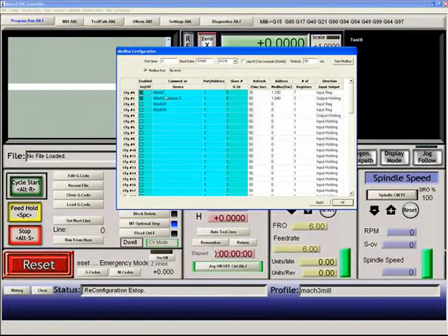These names are usually read by a plugin, and they're really just there as a notification of what you're using it for. I only have two configurations turned on. They're both set to port 1, so that's serial port 1. Slave number 6, which my Mod I/O happens to be set to as a slave number. Yours will probably be a 1 or whatever your slave number is for your Modbus.